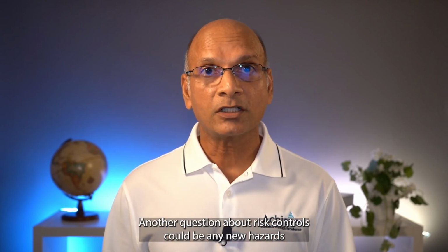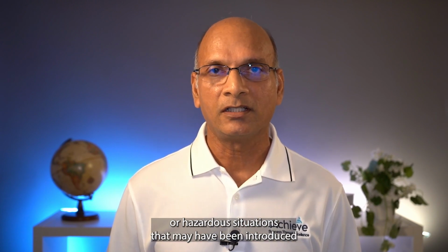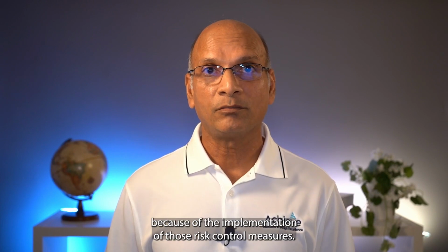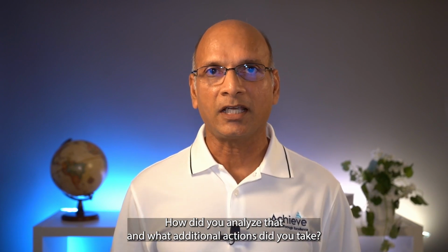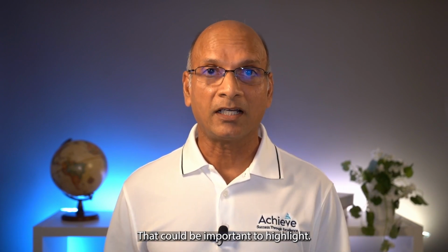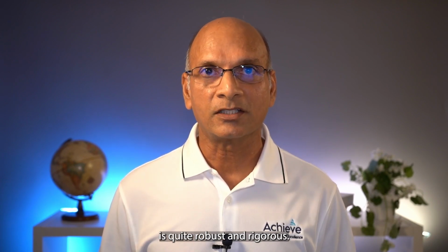Another question about risk controls could be any new hazards or hazardous situations that may have been introduced because of the implementation of those risk control measures. How did you analyze that? And what additional actions did you take? That could be important to highlight, again, in the name of transparency, to be able to show that your process is quite robust and rigorous.